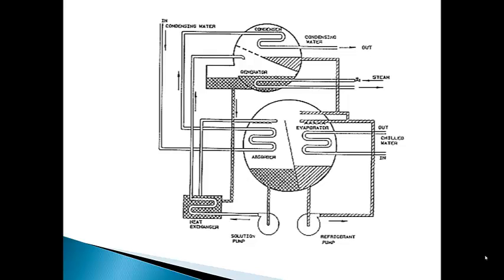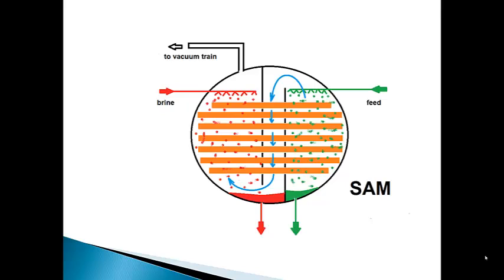Drystill has adapted this concept to an open system through the invention of the SAM, a prototype of which you saw in operation at the start of this presentation. In a 2-dimensional schematic, we show the SAM in this form. Vapors generated in the evaporator are routed to the bottom of the absorber section, so that in order to reach the vacuum pump, they must travel counter-current to the falling absorbent fluid, maximizing the opportunity for absorption to occur. No heat exchange coils are involved.